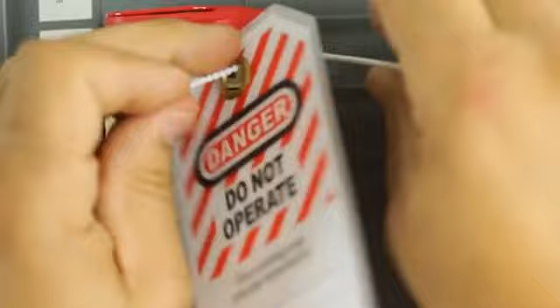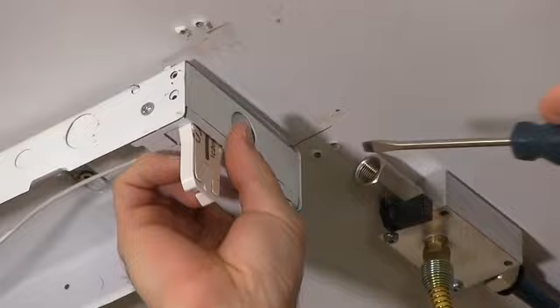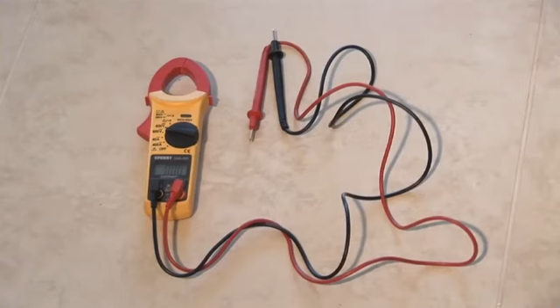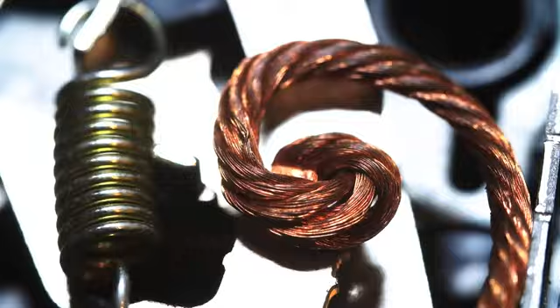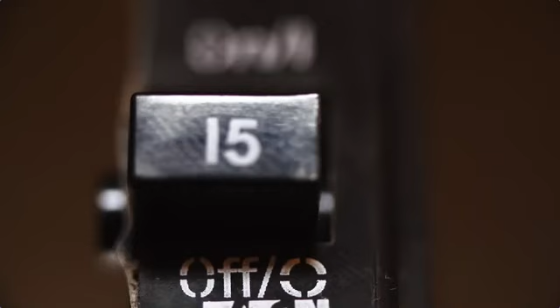Wearing leather or insulated gloves gives you added protection. Use a circuit tracer or meter to verify power is off. When working, make sure you use insulated tools. There is a voltage rating listed on these insulated tools. When using hand tools, double insulated tools will give the best protection. If you need to use a ladder, make sure it is wood or fiberglass, and most importantly, dry.